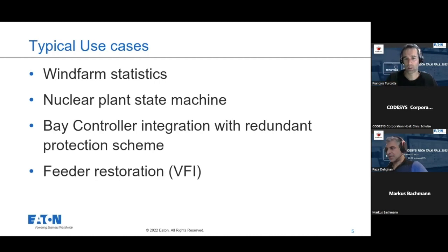Another one is a nuclear plant state machine. I don't have any screen right now, but this is a type of use case where we implement a state machine, basically the same as I explained earlier, where you receive different statuses from the field and make decisions based on them, such as opening a certain breaker, to make sure you're operating correctly. It's really just receiving inputs and defining those algorithms: I'm going to open or close this breaker to allow this power to flow to this transformer or whatever. That's how it's implemented for a nuclear plant, and that's one example.